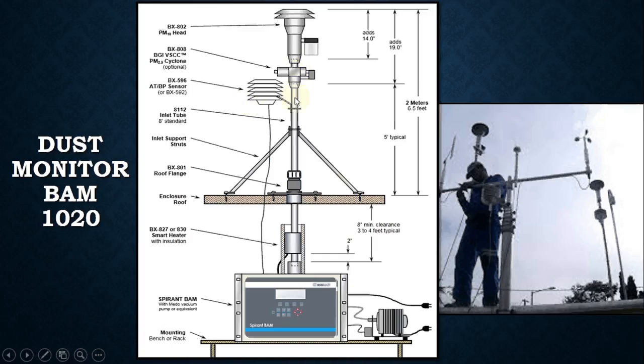The vacuum pump creates a draft of air to flow through the inlet tube. So a draft of air is created in here, in this tube. And the air is first filtered through its inlet filters, so through this filter and this filter. Then it goes through a heater which regulates the humidity of the sample, so that's the heater which regulates the humidity of the sample. And this sample is then analyzed by the dust monitor.